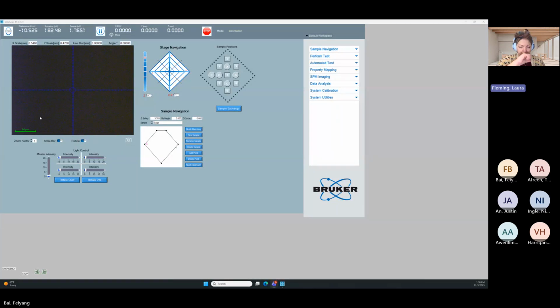Okay, so our first question is: is the hardware installed properly? Is it correct that the tip, a Berkovich probe, is installed in the transducer and that the transducer is installed on the instrument? Yes. Okay, what's on the stage? What do we have for samples right now? The two samples we mentioned are the fused quartz and the aluminum. All right, so question one is done. Is the hardware installed correctly? For our purposes, yes. If it was you, you would also have your sample hopefully on the stage.